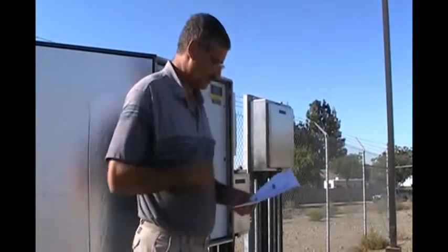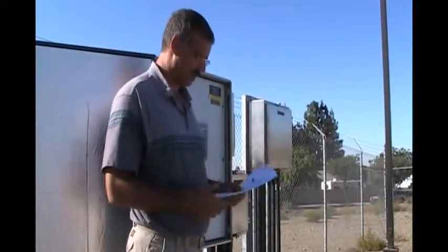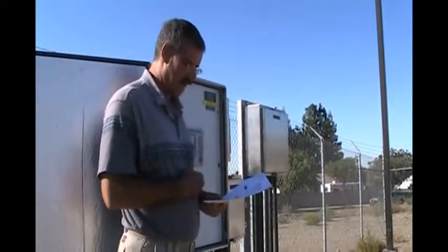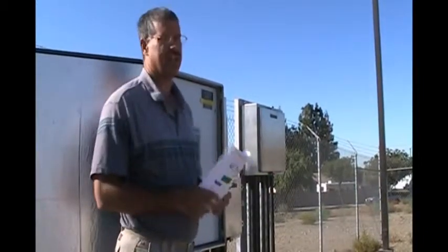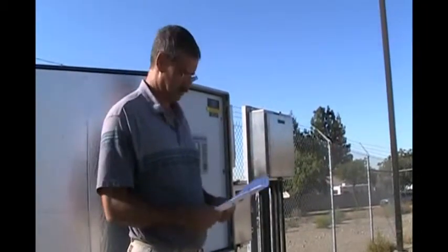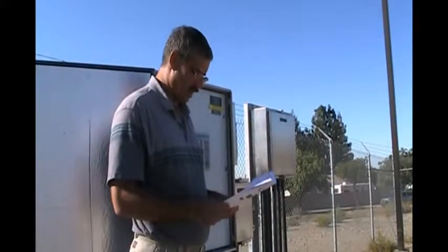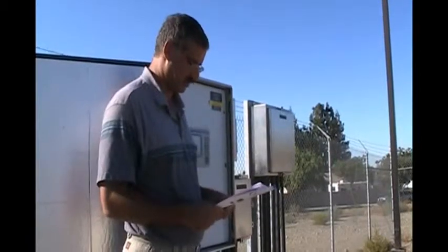The main screen, you'll see on there that it displays the flow set point. It gives you the percentage that the valve is open at the time, the current flow through the valve, and the pressure in PSI and flow, of course, in cubic feet per second. From here, we have the ability to log in again, to change our login if we want higher privilege, if we have a function that we want to gain access to that we don't have available to us. There's a valve control screen button, a set point screen, site lockout, intrusion alarm reset, and system trend analysis, and we'll go through each one of those in detail.